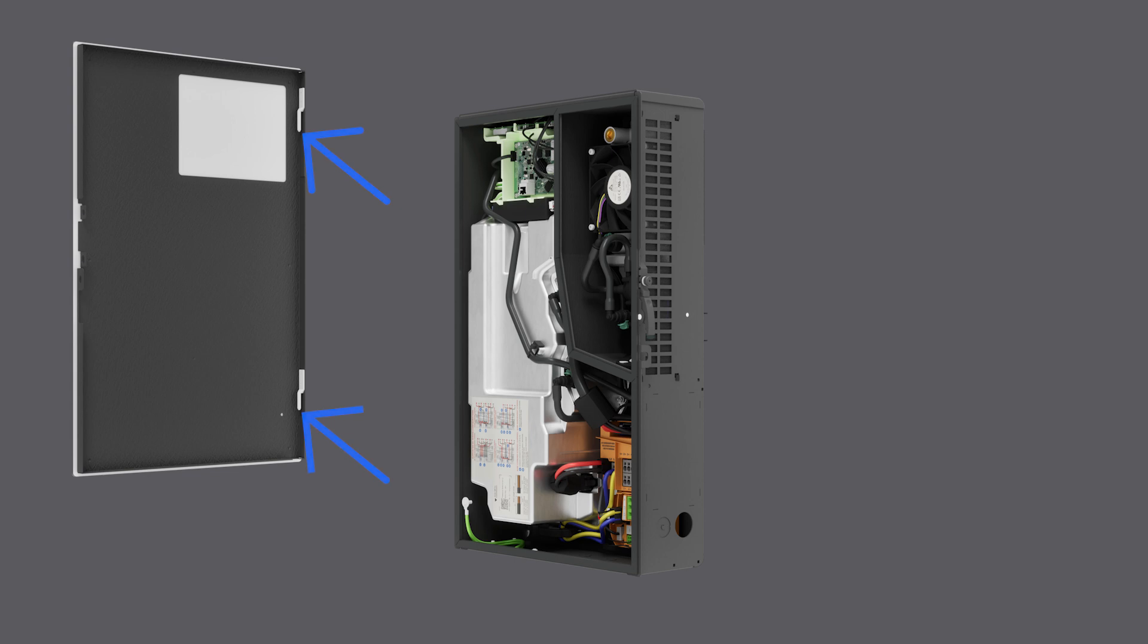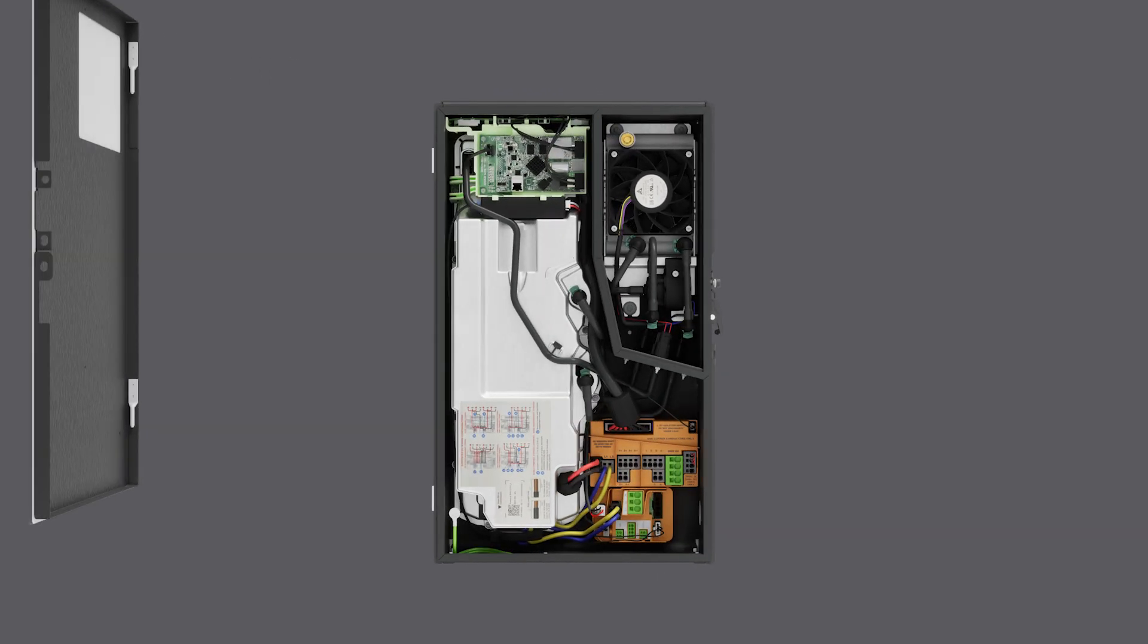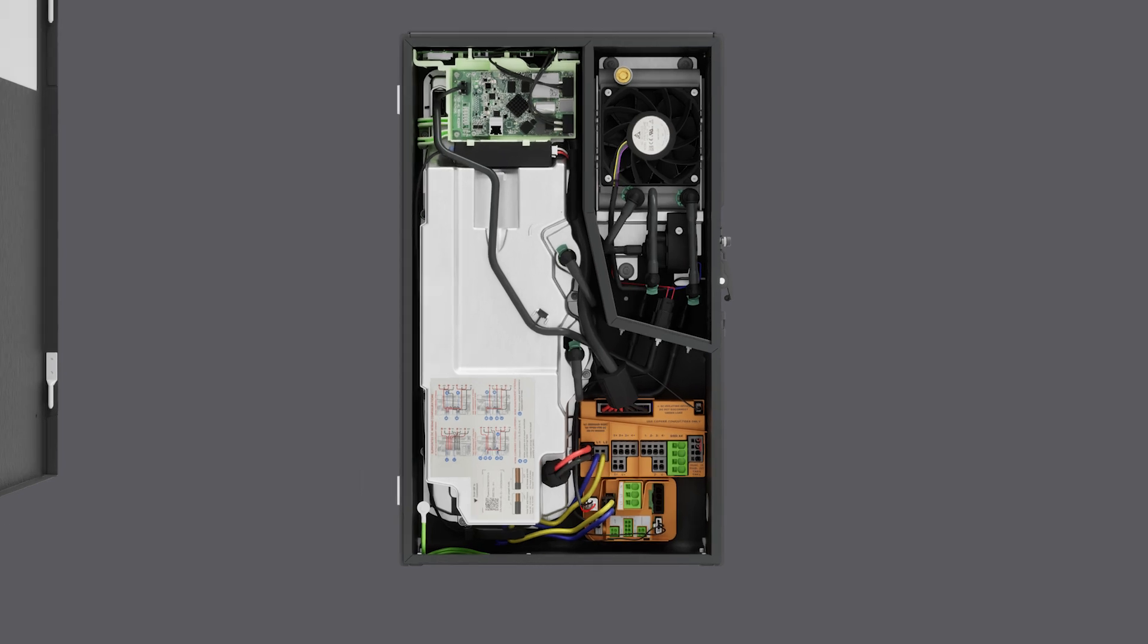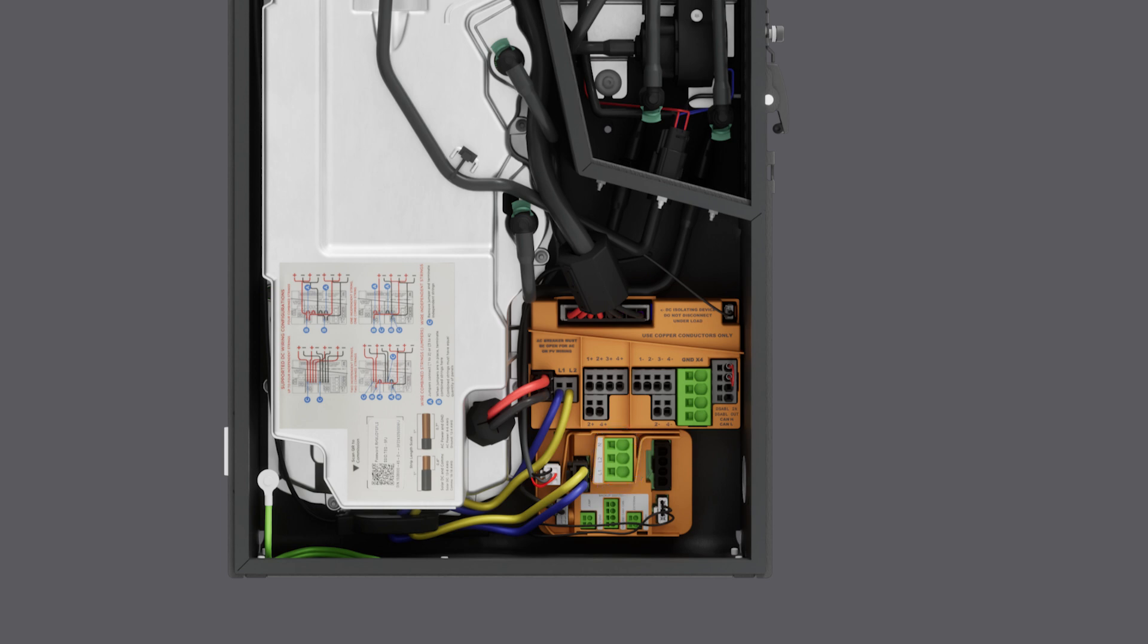Behind the front cover are all of the field-accessible internal components. This terminal block is used for the direct current conductors coming from the solar array. This terminal block is used to connect the alternating current output to the interconnecting breaker or disconnect. Equipment grounding conductors are terminated here. When a system shutdown switch is installed, it is connected to these terminals.